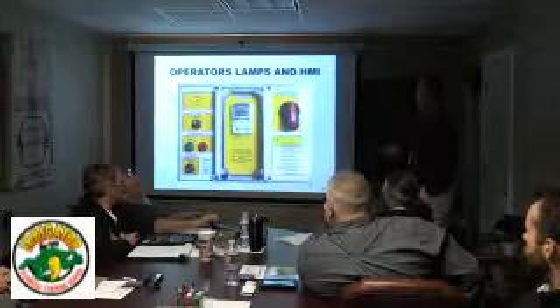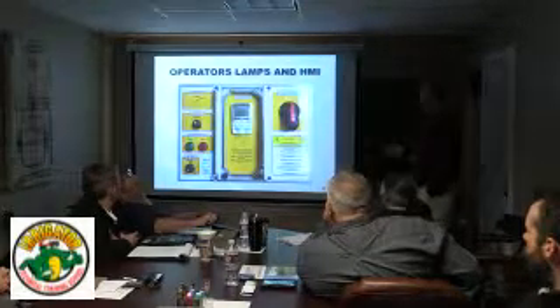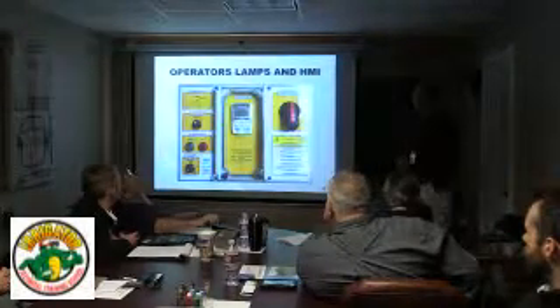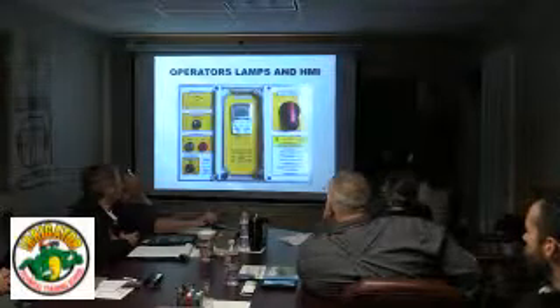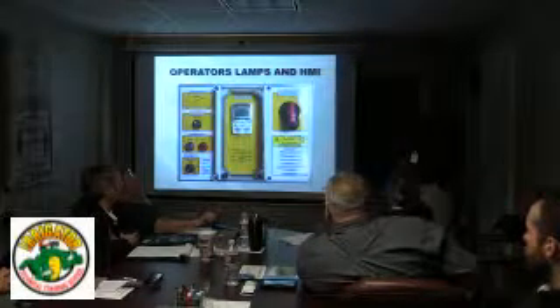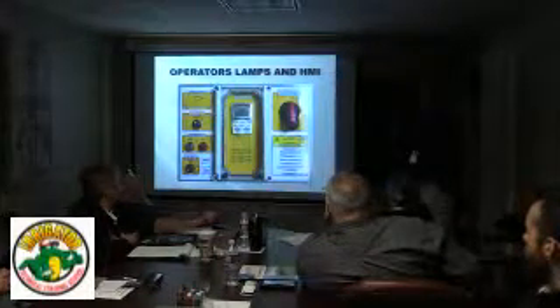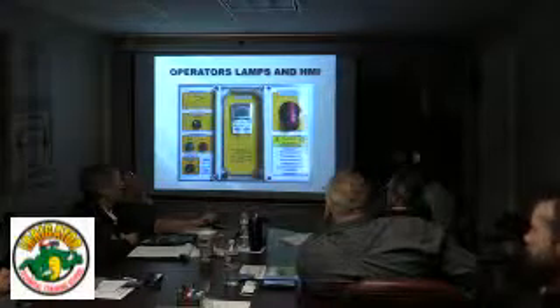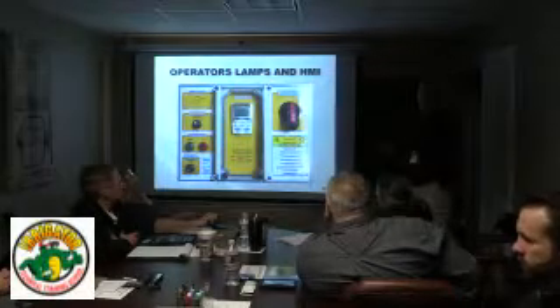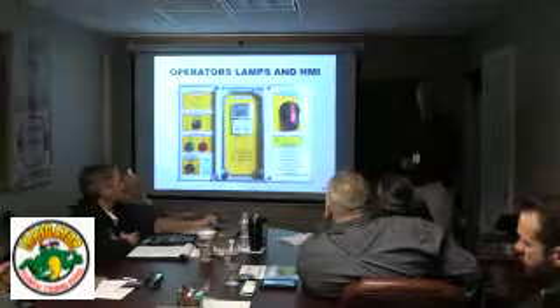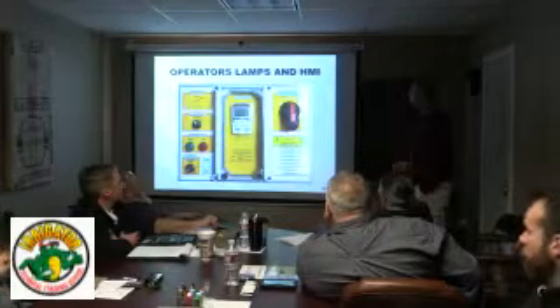So if you come up to a panel like this and it does have the local remote switch on it and it's not starting, you can just quickly switch it to local and see if it starts or not. If it starts, you know it's something to do with that remote signal coming from the clock or something. If it doesn't, then you're going to be looking at the control panel or drive or something.